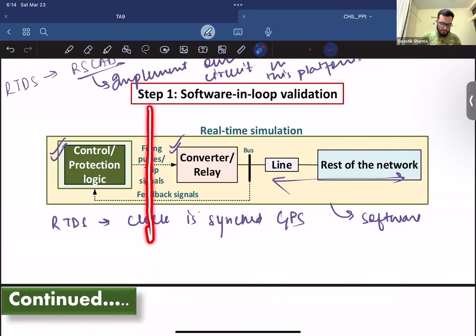This control or protection logic is implemented on a digital signal processing (DSP) board, outside of the software. Now your RTDS communicates directly with your DSP board, which is simulating the rest of the network inside the RSCAD platform. The converters and rest of the network remain in the software, running in real-time simulation, but the device under test—the logic you're proposing—is moved outside the software.